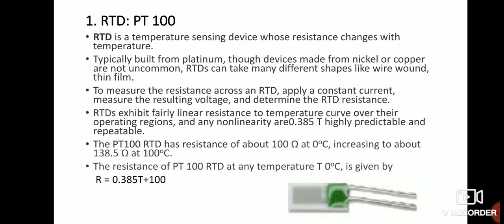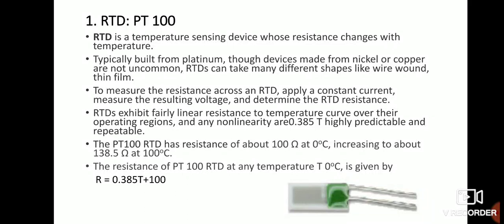The first type of sensor is the RTD, that is the Resistance Temperature Detector. An RTD is a temperature sensing device whose resistance changes with temperature. Typically it is built from platinum, nickel, or copper, and can take many different shapes like wire wound or thin film. To measure the resistance, apply a constant current through the RTD, then measure the voltage across it.